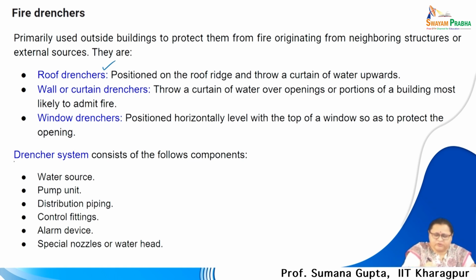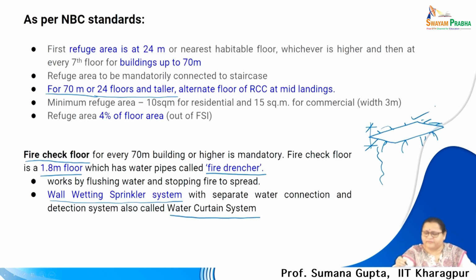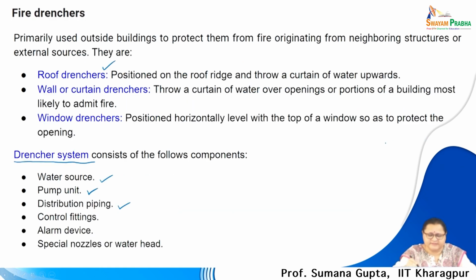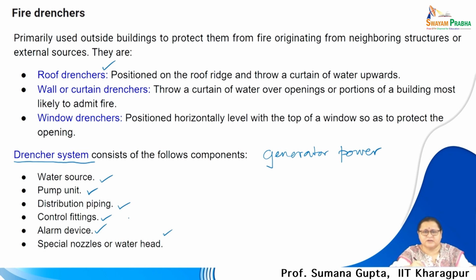Now, remember, for such drenching systems, you have to have a water source, a pump unit, and a distribution pipe, which I had drawn here. You have to have a water supply to this, control fittings, alarm devices and special nozzles or water heads, because these will force water into the entire facade. All these should be connected to the generator power, because without that the alarm will not actuate. Once it is actuated, the pump will also actuate to maintain the water pressure and to flush the entire building facade.